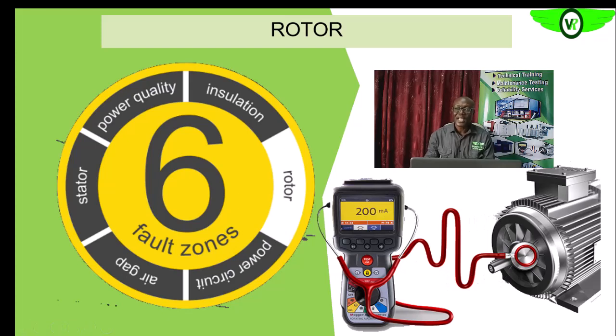We use the Megger MTR105. The MTR105 can assist us in doing this, because we check the inductance, the rotor influence: how the change in the rotor position affects the inductance of the stator winding. Are we getting it? So as we rotate and take the reading, we'll see the rotor influence on that inductance. When there are problems, especially when the residual flux or magnetic field in the rotor is more than what is normal, we'll see it during that rotor influence test.